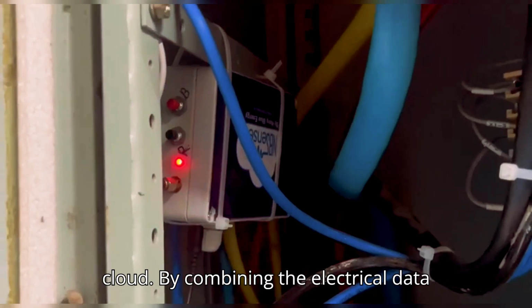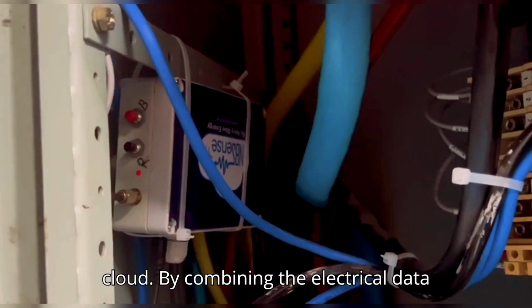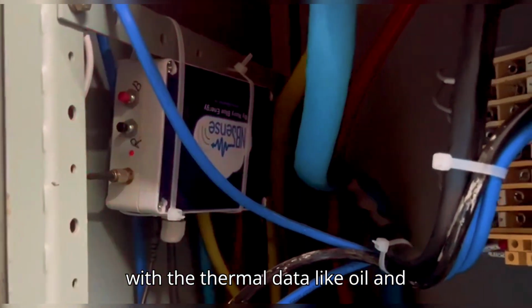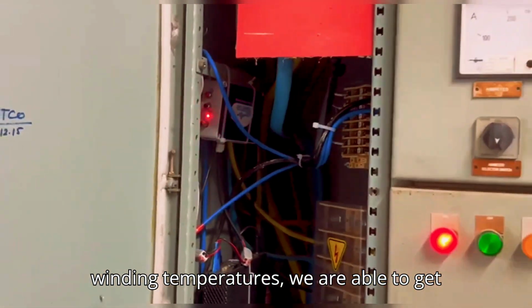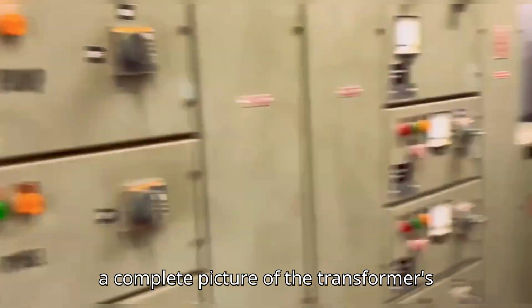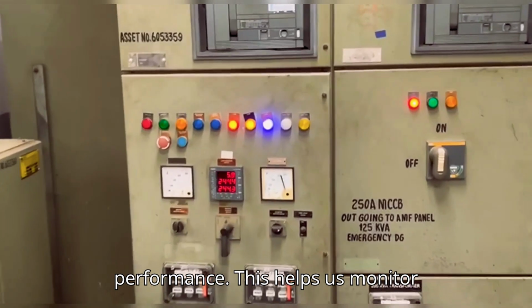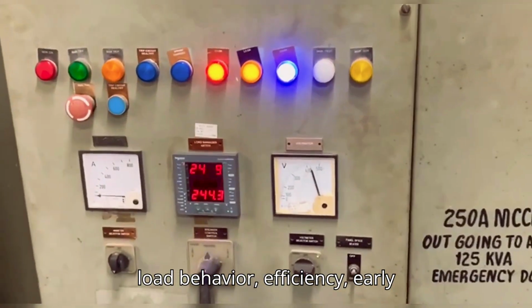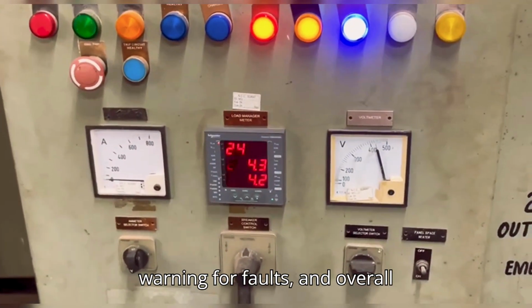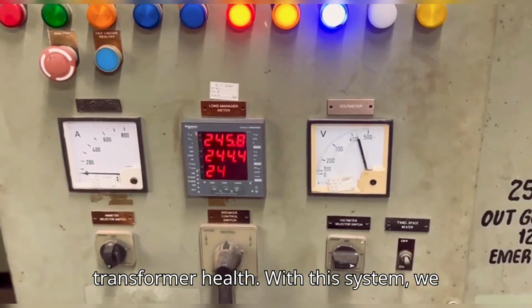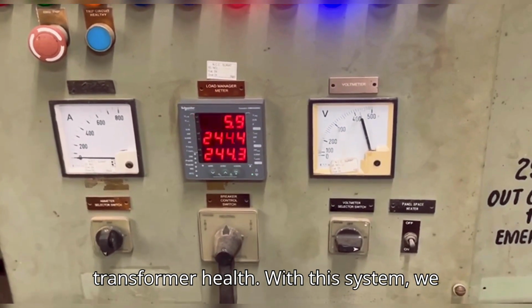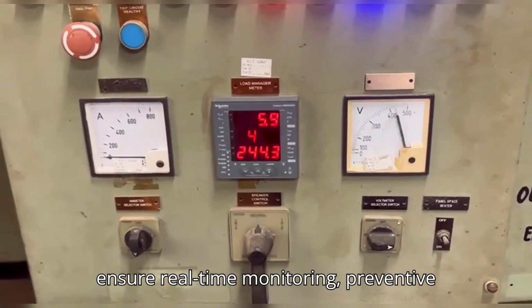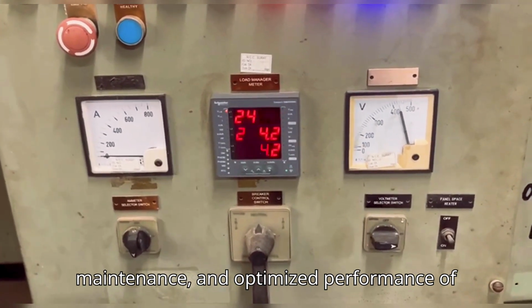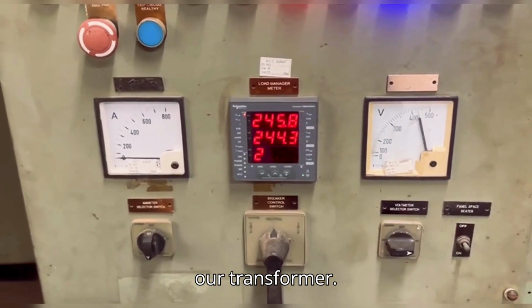to the NBSense cloud. By combining the electrical data with the thermal data like oil and winding temperatures, we're able to get a complete picture of the transformer's performance. This helps us monitor load behavior, efficiency, early warning for faults, and overall transformer health. With this system, we ensure real-time monitoring, preventive maintenance, and optimized performance of our transformer.